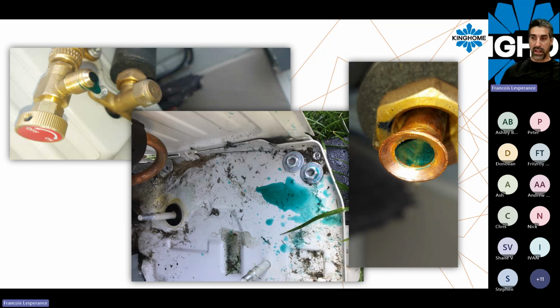So you can have a compressor burn out in a couple of years, maybe 2 or 3 years after this unit was installed. So if you have to do a retrofit or you are going to change a unit, you may find this kind of discoloration inside the copper tube. Well, you need to make it clean again.